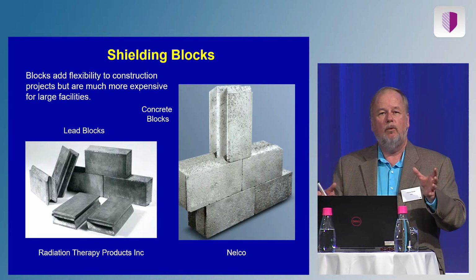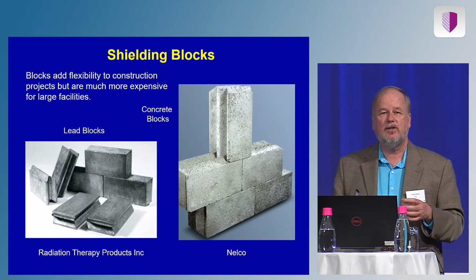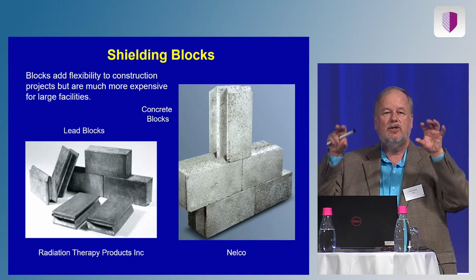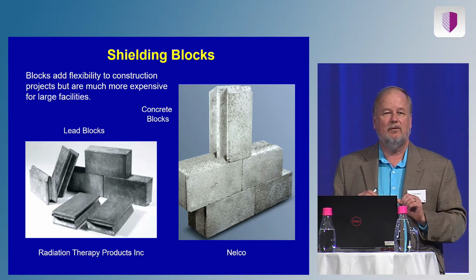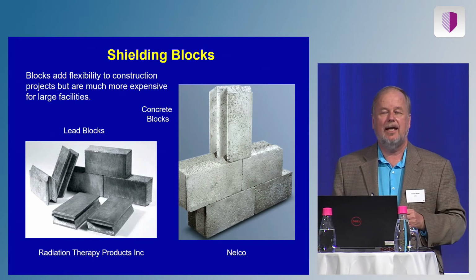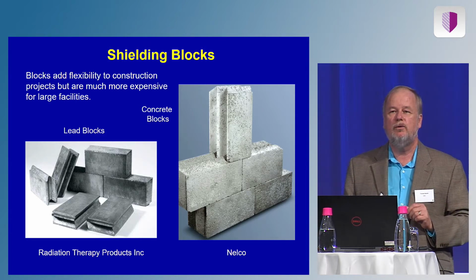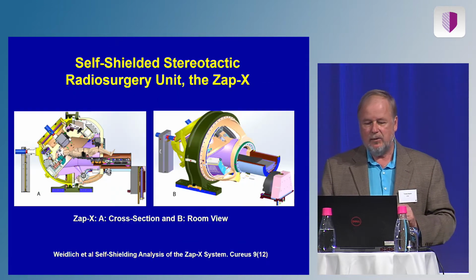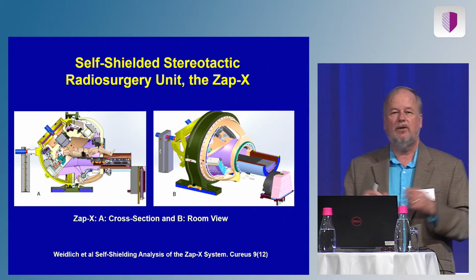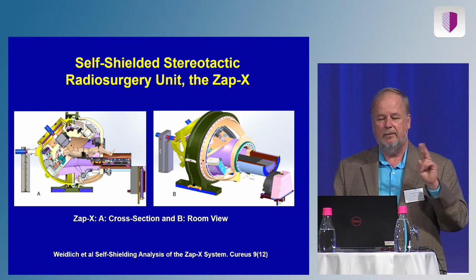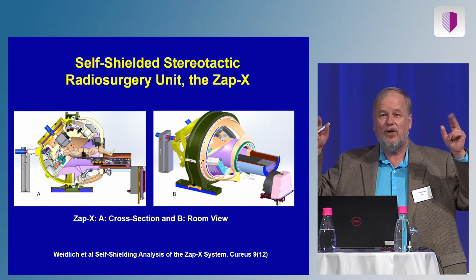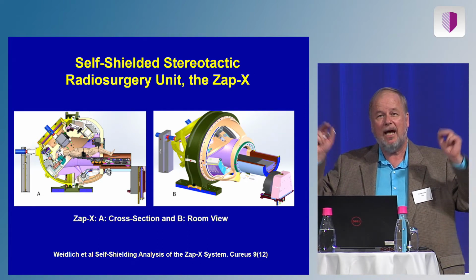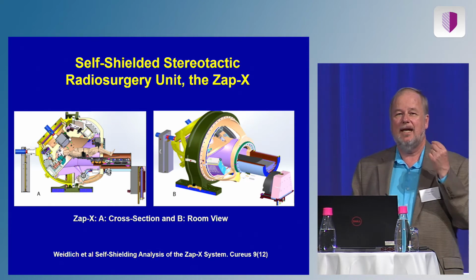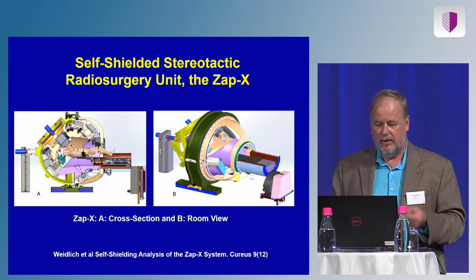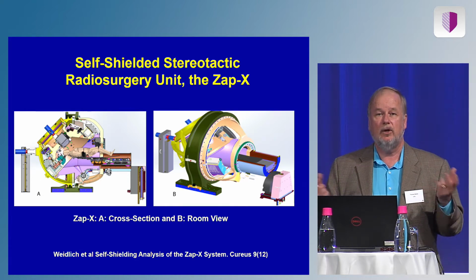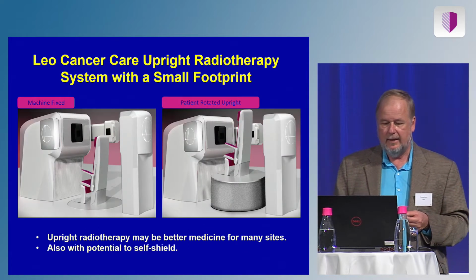When you actually design the vaults for this, you can literally put 2 machines in a classical vault now, and add shielding blocks inexpensively to get two vaults instead of 1. And interestingly, there's actually a self-shielded machine under development. In fact, two of them. This one's completed. This is the so-called, unbelievably, this is its name, ZapX. The ZapX is designed for stereotactic radiosurgery, and it's self-shielded. You can go into a conventional room without shielding.